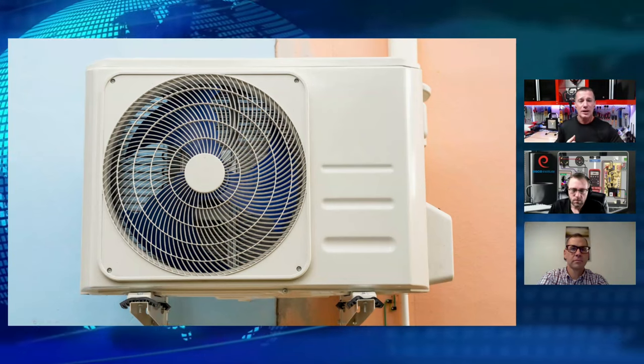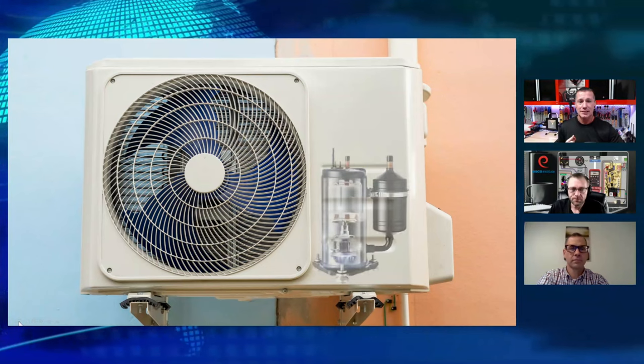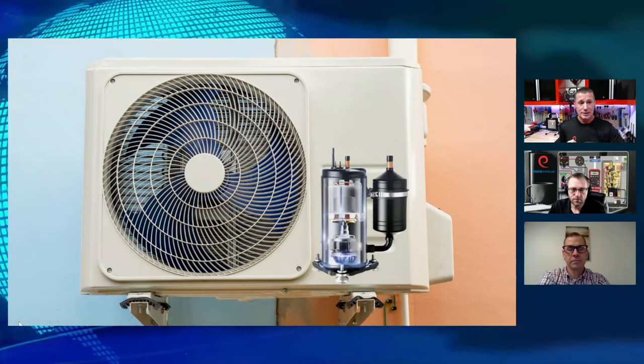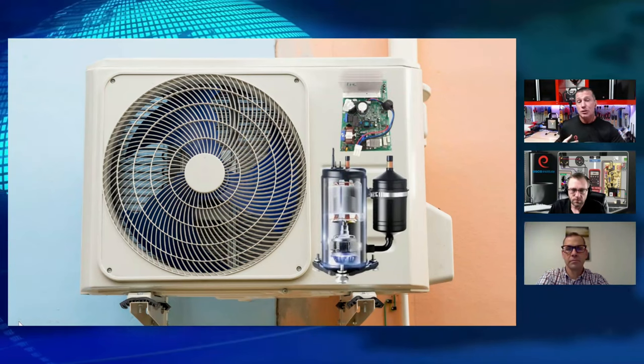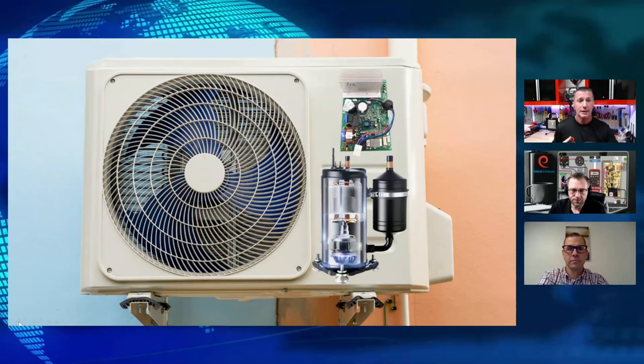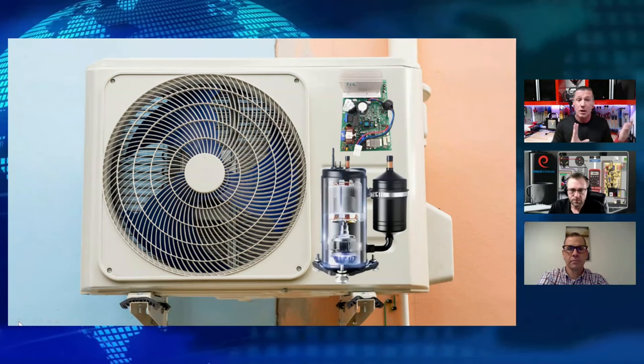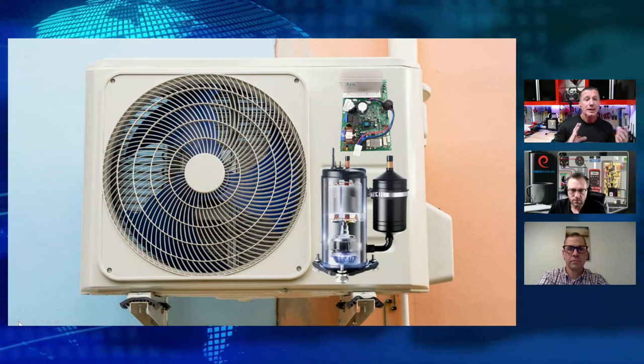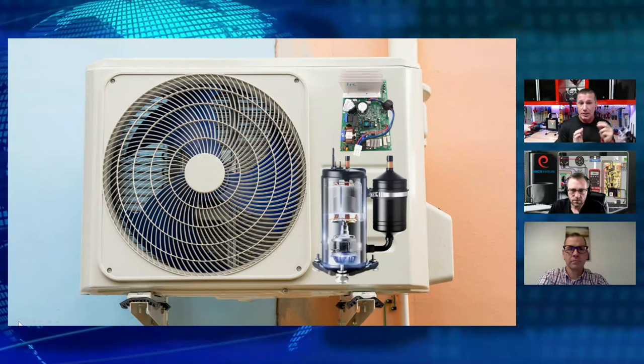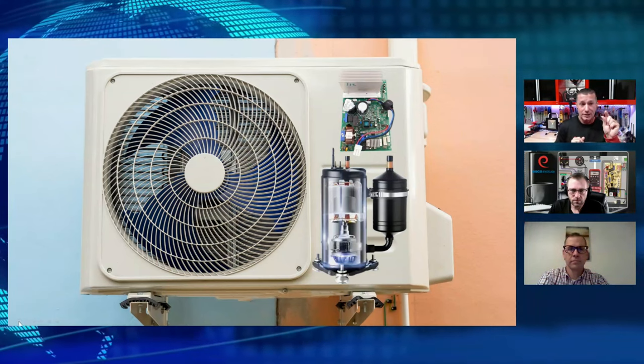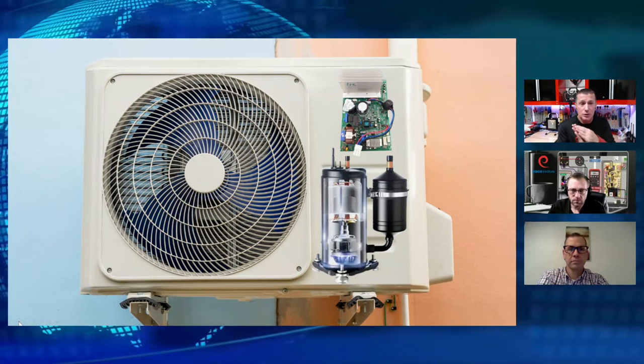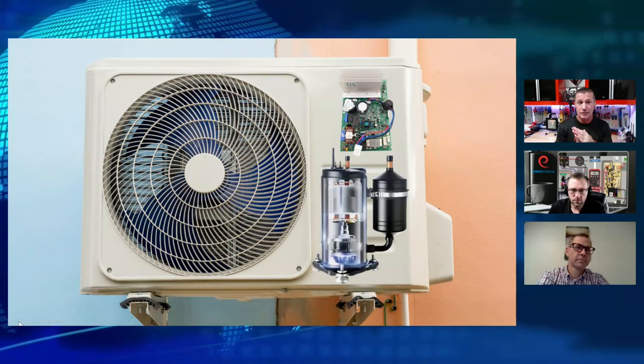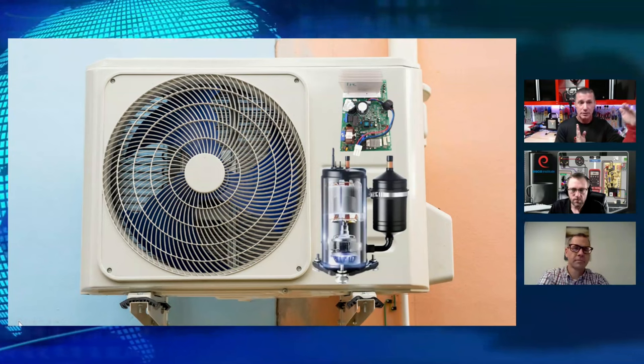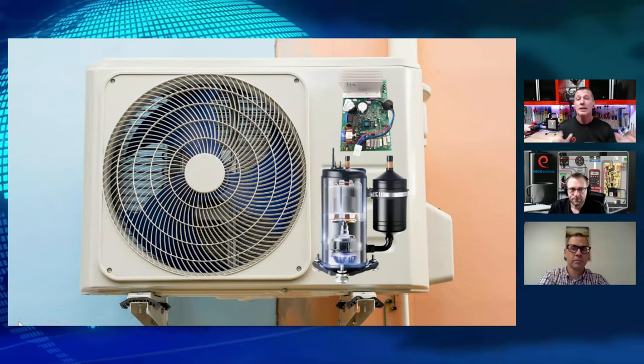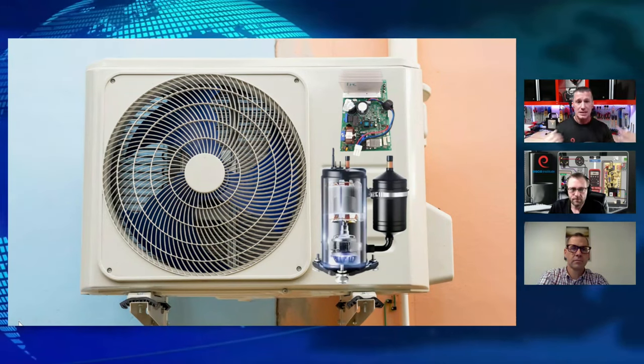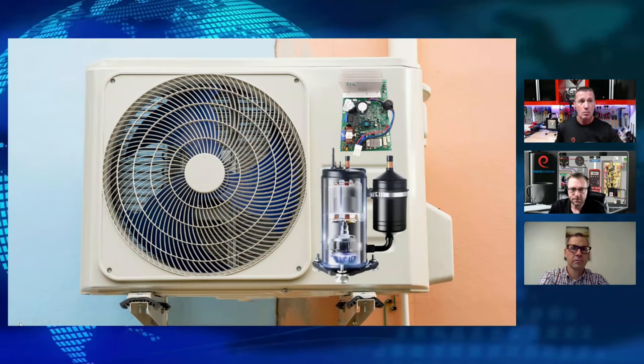Anytime we're talking about an inverter-driven system, we're talking about a compressor that has variable rotation being driven by an inverter board. So when you listen to a mini split, it never starts up on 100% capacity. It always starts at a reduced capacity. It might hit 100% for a fraction of a second to get it moving, but then reduces back down, a lot of them to 25 to 35% capacity, and then increases as we go. So we're reducing the inrush of current on that electrical motor.